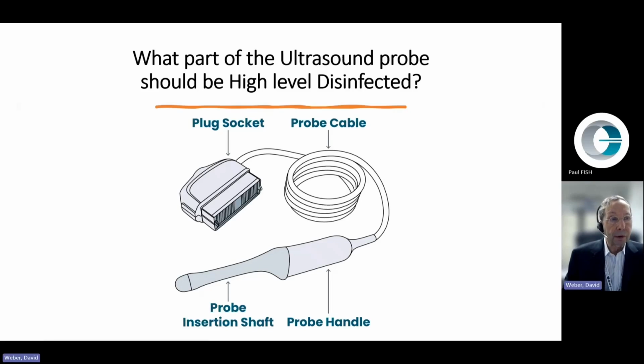So what part of the ultrasound probe should be high-level disinfected? Well, we have the probe insertion shaft, we have the probe handle, and we have the probe cable, which then leads to a plug socket, obviously, to provide electricity for the probe.